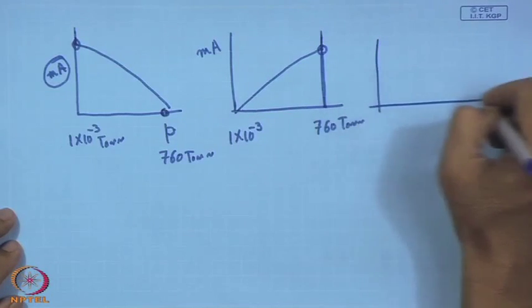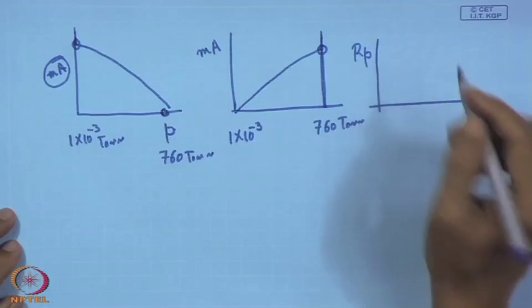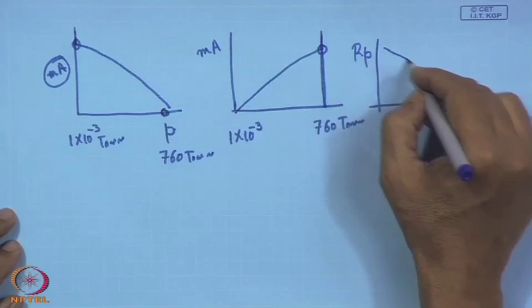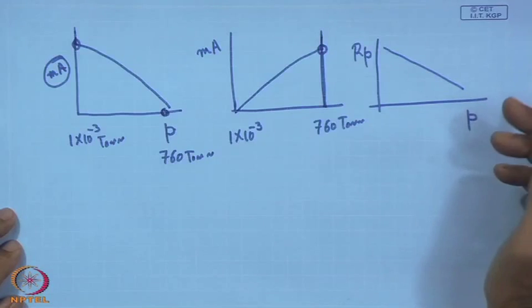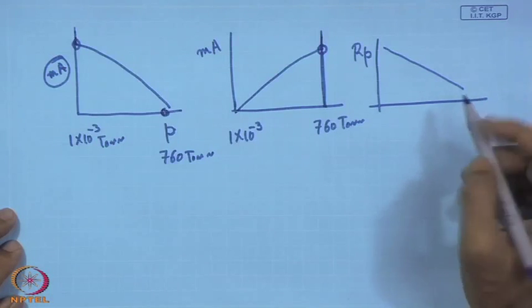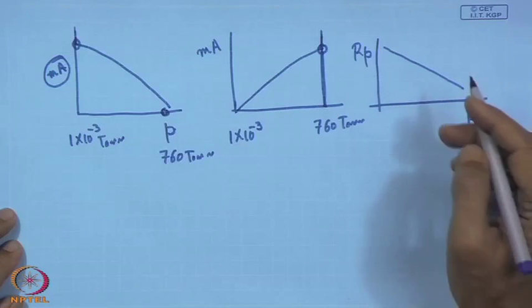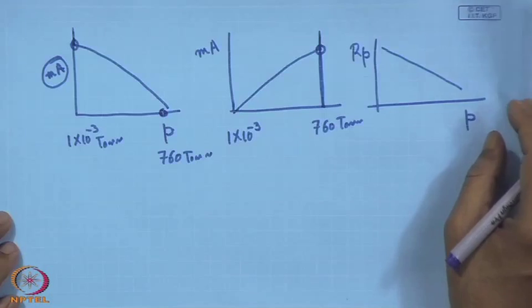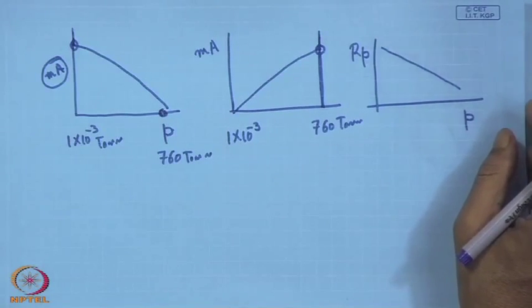In fact, the resistance Rp of this Pirani gauge decreases with pressure, because of the simple reason that the cooling effect is less. So, the resistance will be heated, and as a result this resistance value will keep on increasing, and that helps in getting this error signal.